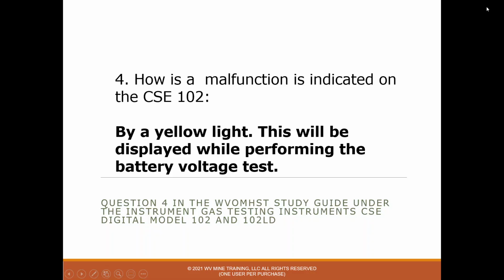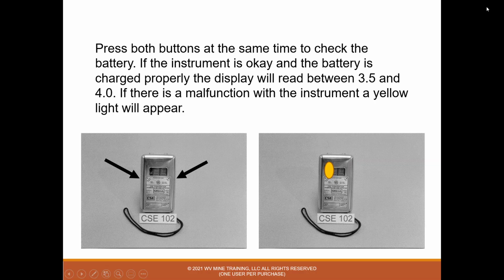Question 4, how is a malfunction indicated on the CSE 102? And the answer is by a yellow light, and this will be displayed while performing the battery voltage test. So press both buttons at the same time to check the battery. If the instrument is okay and the battery is charged properly, the display will read between 3.5 and 4. If there's a malfunction with the instrument, a yellow light will appear.